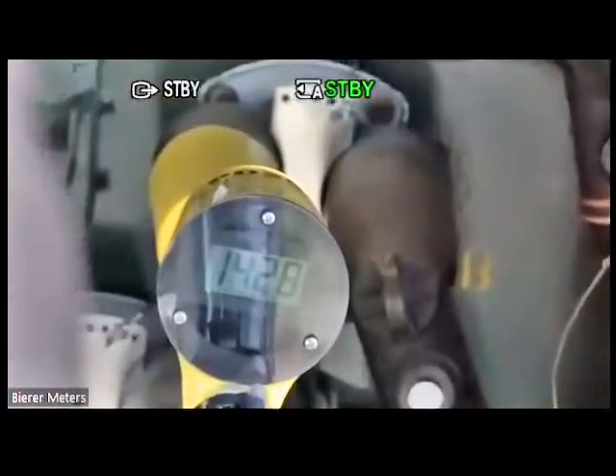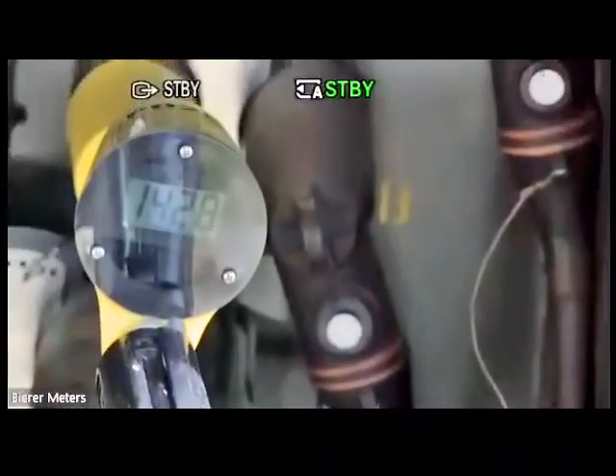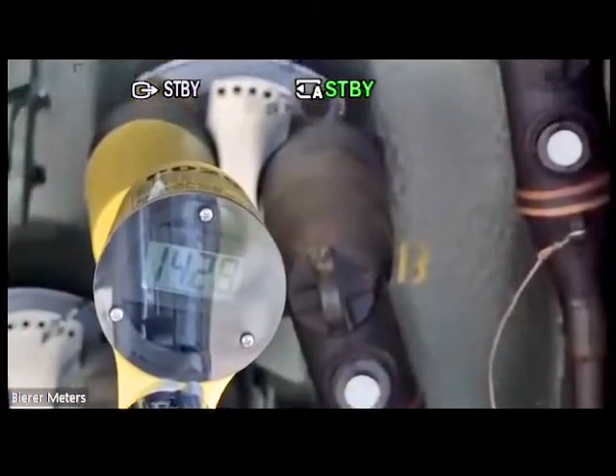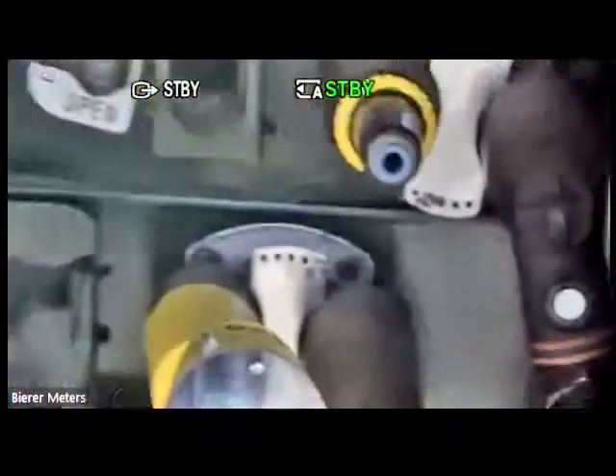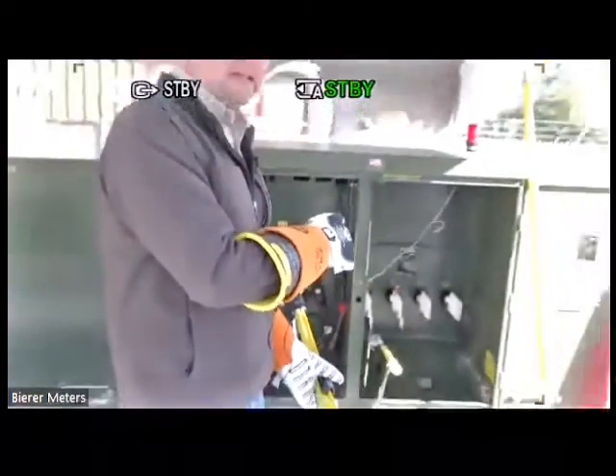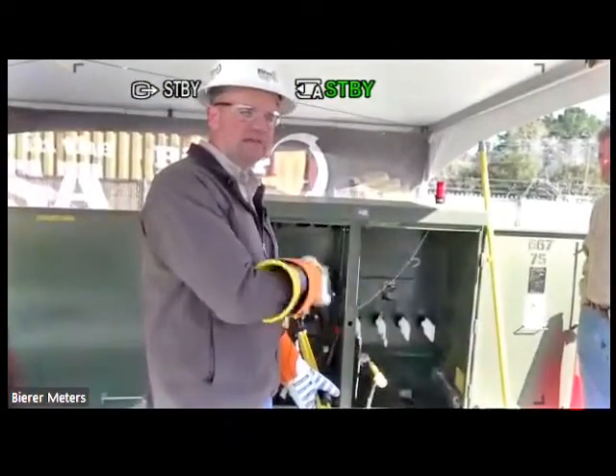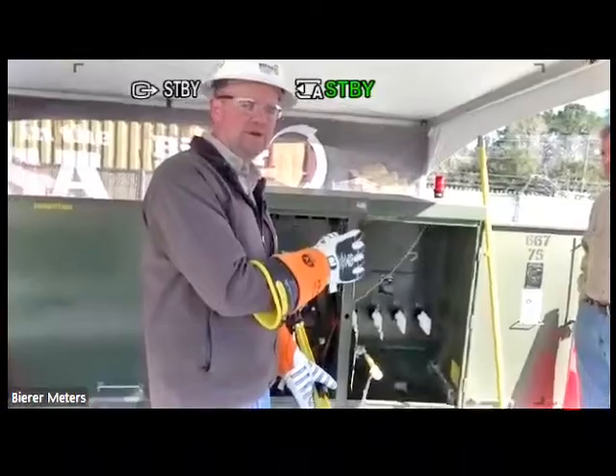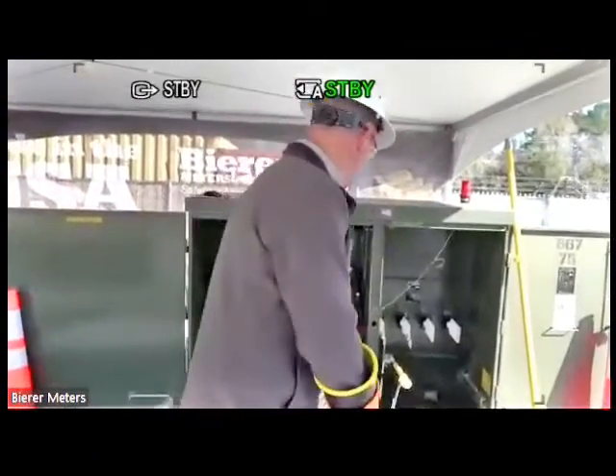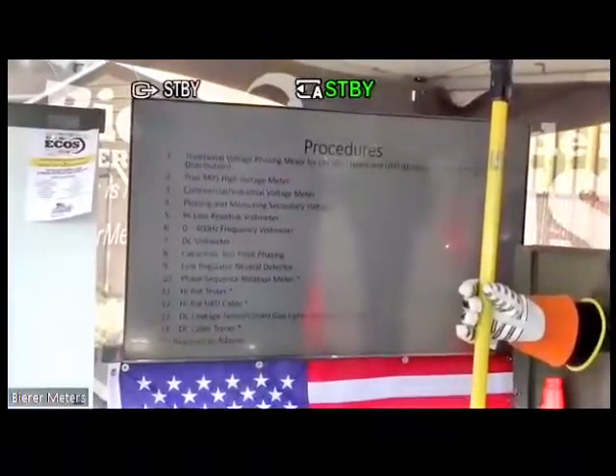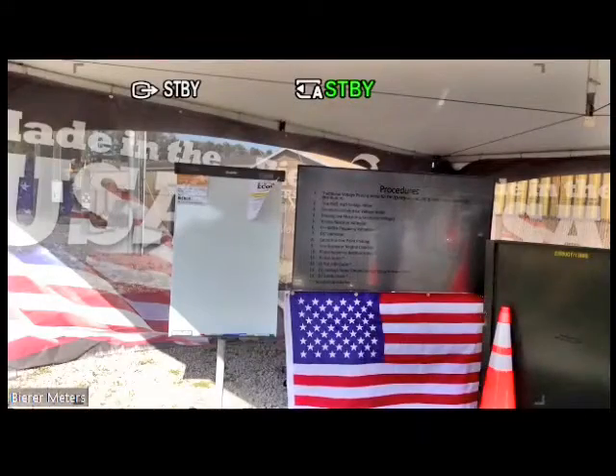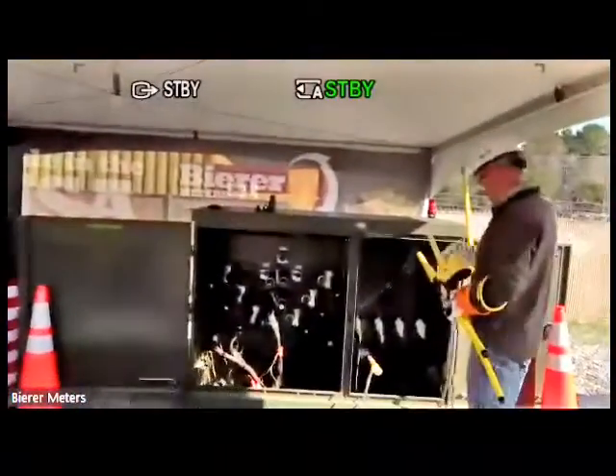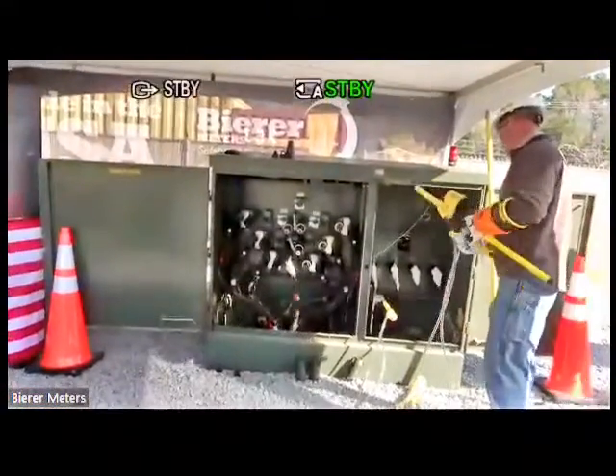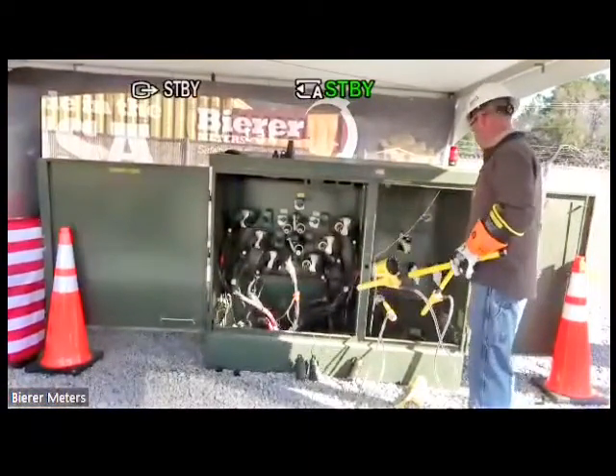14,270, 280 volts. All right, so that number is going to be within 1%. Highline resistive voltmeter, again using an alligator clamp on one end, cable, interconnect cable at any length up to 100 feet to your meter probe. So phasing and measuring secondary voltages in the 2 kV switch position. And I can do my phase to ground potentials or phase to phase.